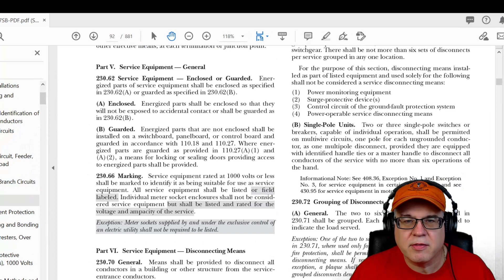And that says: 2 or 3 single pole switches or breakers capable of individual operation shall be permitted on multi-wire circuits, 1 pole for each ungrounded conductor, as 1 multi-pole disconnect, provided they are equipped with identified handle ties or a master handle to disconnect all conductors of the service with no more than 6 operations of the hand.